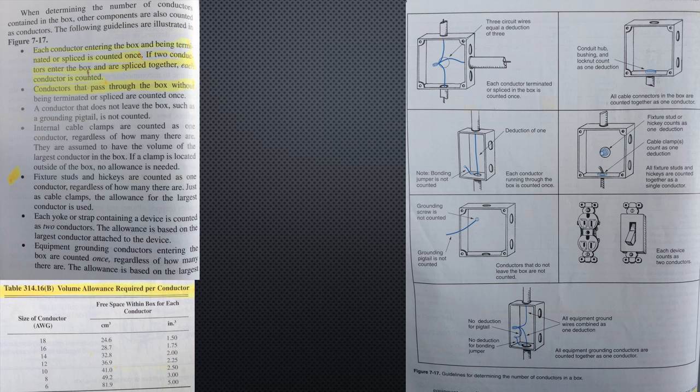Internal cable clamps are counted as one conductor, regardless of how many there are. They are assumed to have the volume of the largest conductor in the box. If a clamp is located outside of the box, no allowance is needed.